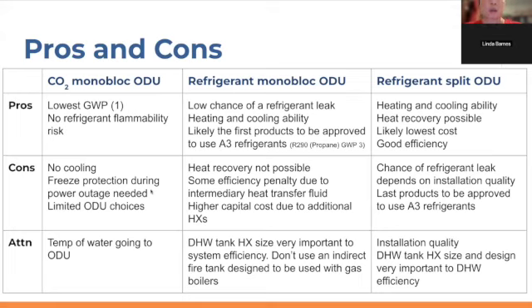Now, one of the advantages of the refrigerant monoblock outdoor units is that there is a low chance of refrigerant leak, because all the refrigerant connections are made in the factory. All those connections have been tested using extremely sensitive robotic, standardized test methods, so they're made perfectly. They don't use CO2, but instead use refrigerants like R32, 454B, or propane. These refrigerants in the standard refrigerant cycle very easily allow heating and cooling ability. So they offer heating and cooling as a function.